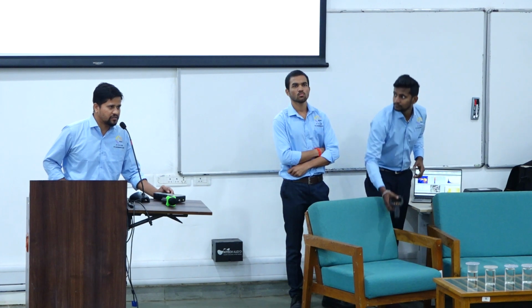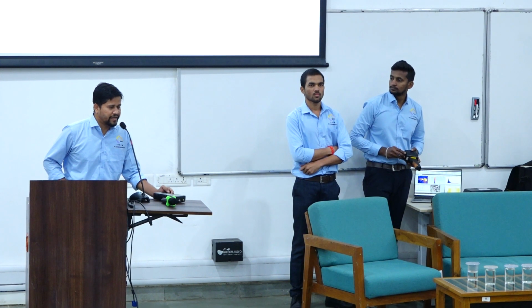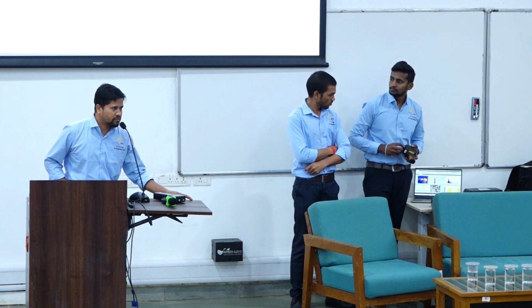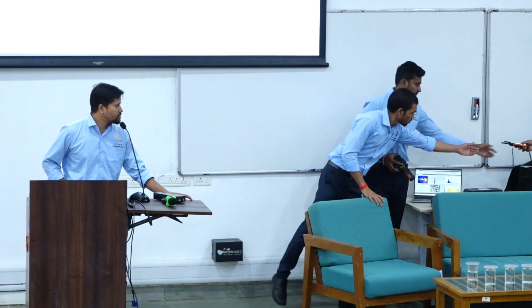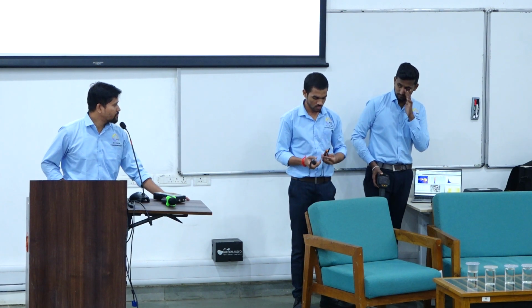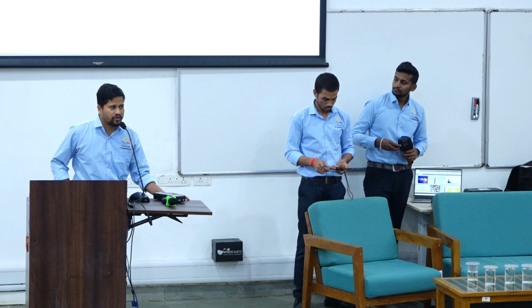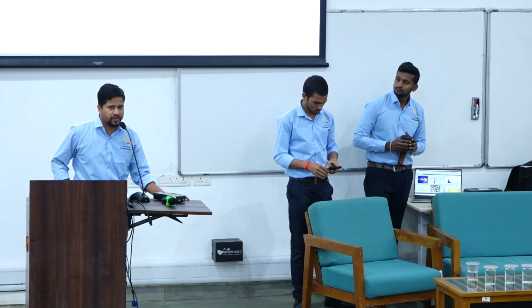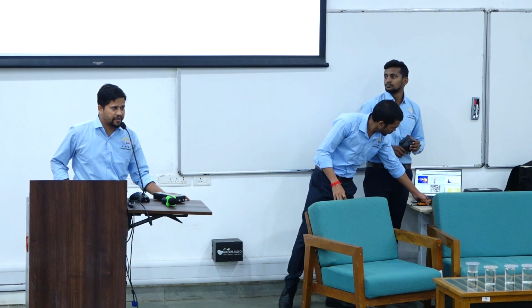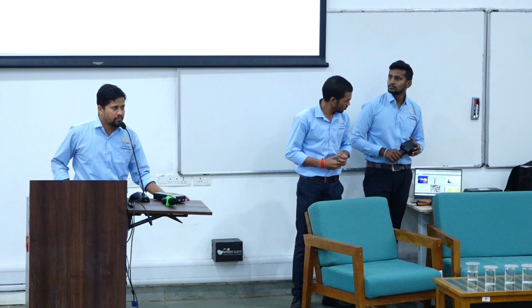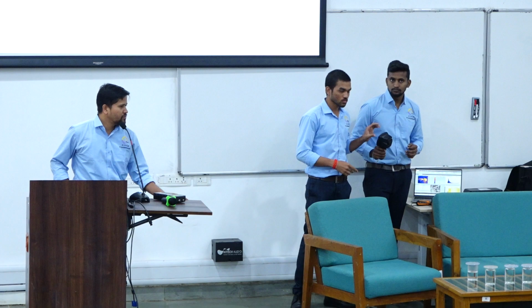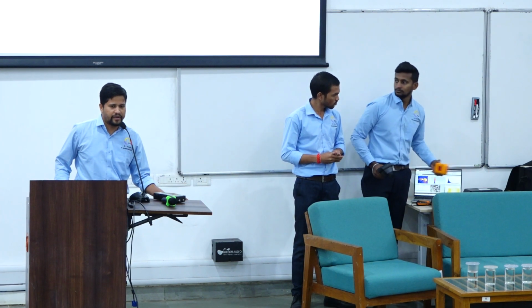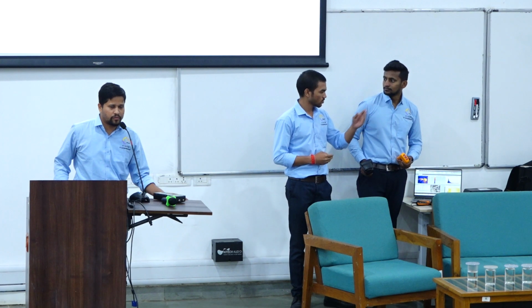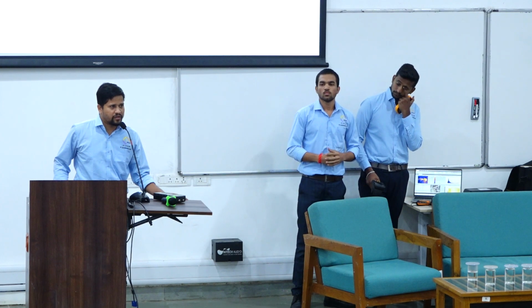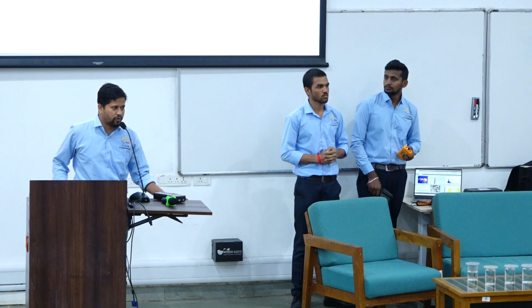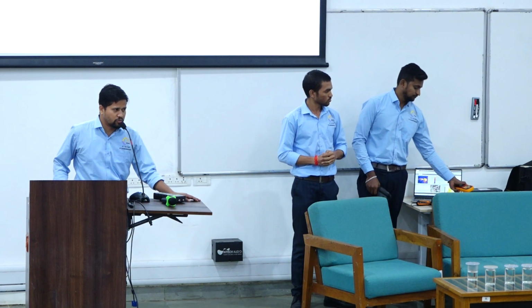For chiller and HVAC analysis, we also have a very dedicated instrument with data logger facility, that is a thermal hygrometer and thermal anemometer. And when we go for measuring with the water flow meter, we first need to identify the thickness of the pipe. For this, we have a dedicated instrument, the thickness gauge. For motor RPM measurement, we have a tachometer and a stroboscope, both. With these instruments, we can compare the measured RPM to the rated RPM of the motor.